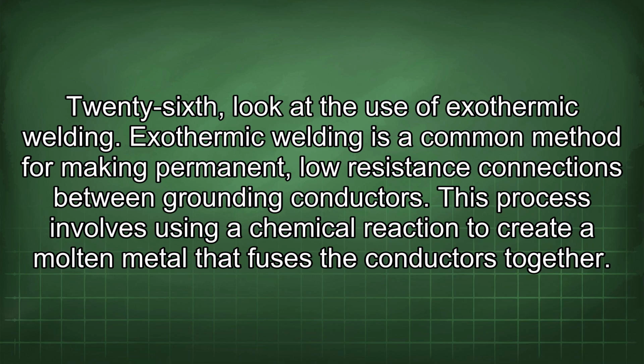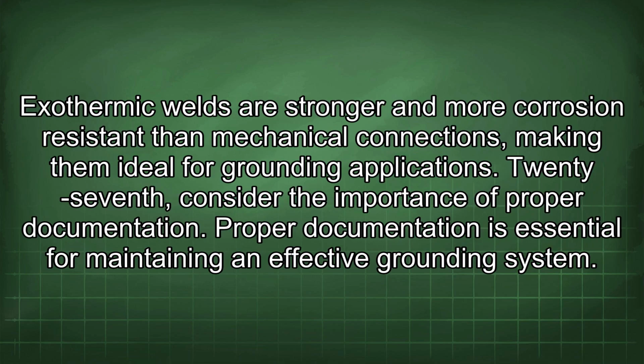26. Look at the use of exothermic welding. Exothermic welding is a common method for making permanent low-resistance connections between grounding conductors. This process involves using a chemical reaction to create a molten metal that fuses the conductors together. Exothermic welds are stronger and more corrosion resistant than mechanical connections, making them ideal for grounding applications.